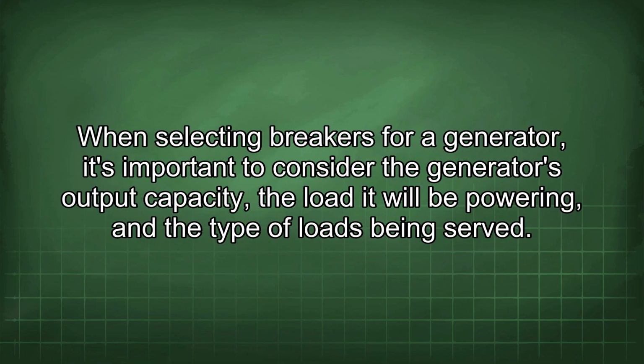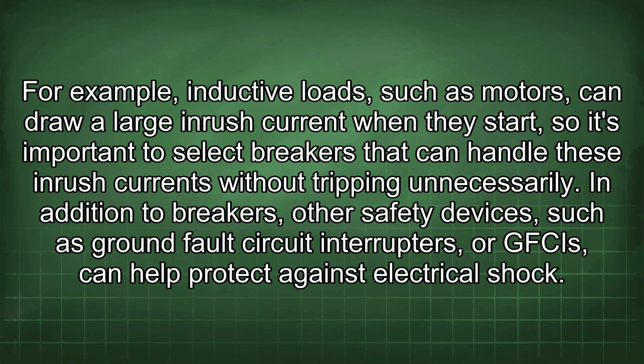When selecting breakers for a generator, it's important to consider the generator's output capacity, the load it will be powering, and the type of loads being served. For example, inductive loads, such as motors, can draw large inrush current when they start, so it's important to select breakers that can handle these inrush currents without tripping unnecessarily.